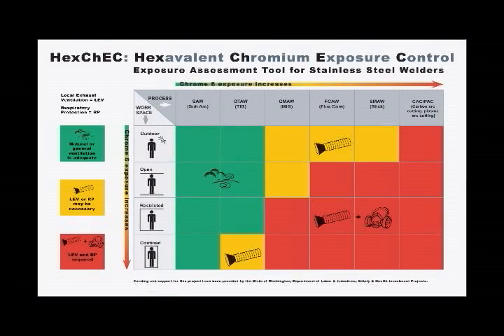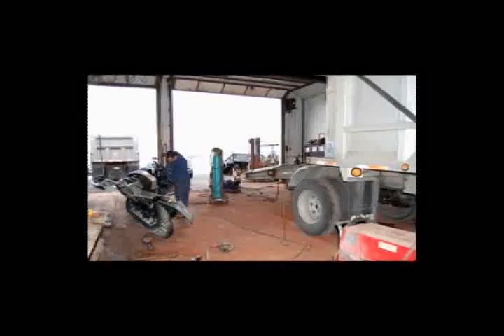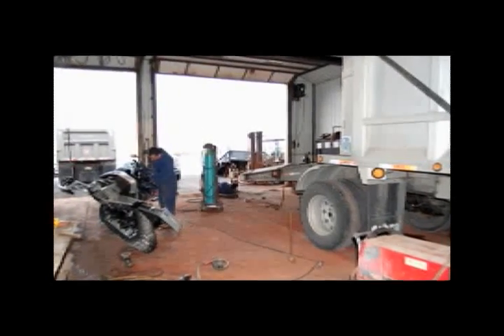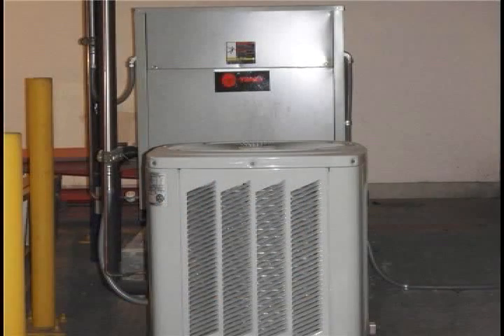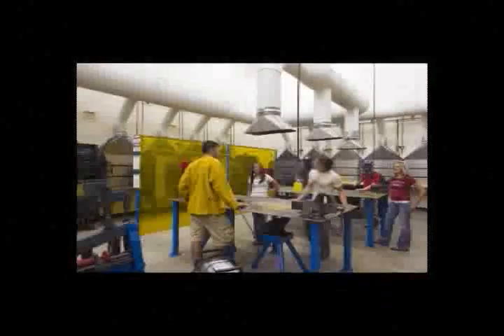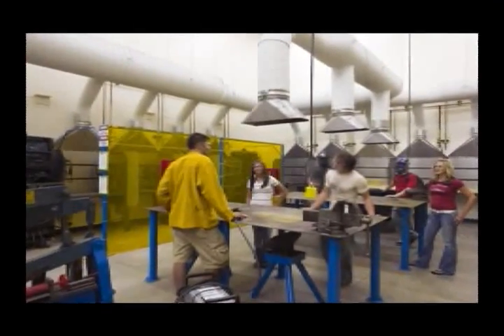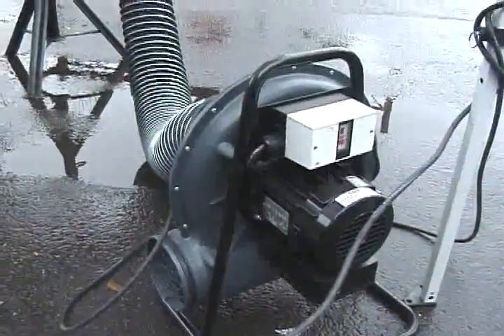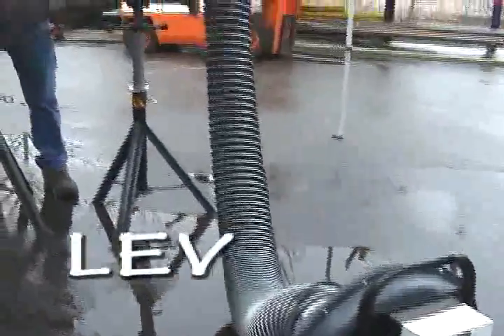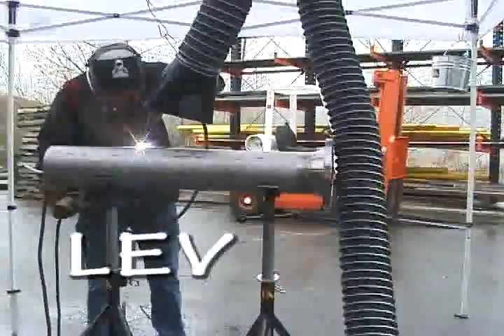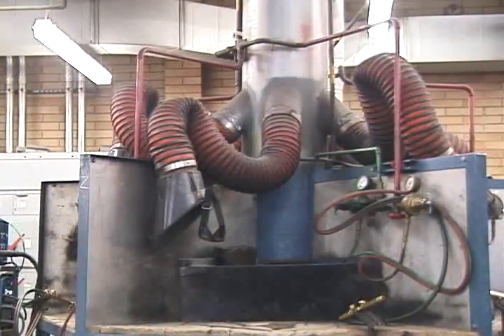Before we go into more detail on LEV, let's first talk about natural ventilation. Natural ventilation occurs when air enters through open windows or doors. General ventilation uses a fan or HVAC system to move large quantities of air to dilute contaminants. It does not capture the contaminants at their source. More efficient and often cheaper than general ventilation is local exhaust ventilation, or LEV. LEV is used to control contaminants in the workspace at their source. LEV is an important engineering control because it removes contaminants before they reach your breathing zone.